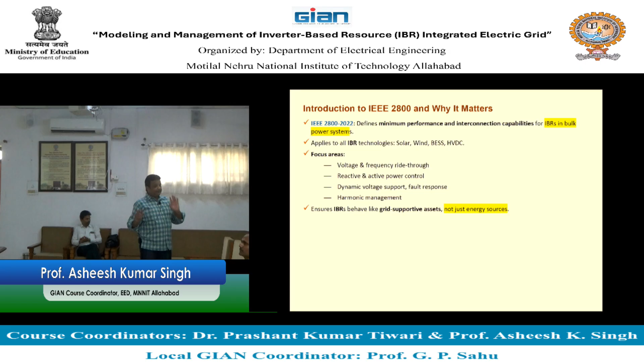What does IEEE 2800 require from IBRs? What information do they need and what actions do they demand, right? The ability is frequency ride-through, and the requirement is to stay connected and inject power during deviations. Clear? So the grid codes of the European countries, as I was asking, every country has its different codes, right? So they decide at what point of this code, there is a grid code plot, at what time of this plot you can enter the grid or you can leave the grid. This is a mandatory condition for the IBR-based generating stations, means these DGs. Clear? And IEEE 2800 is the next stage in that series, in that direction you can say.